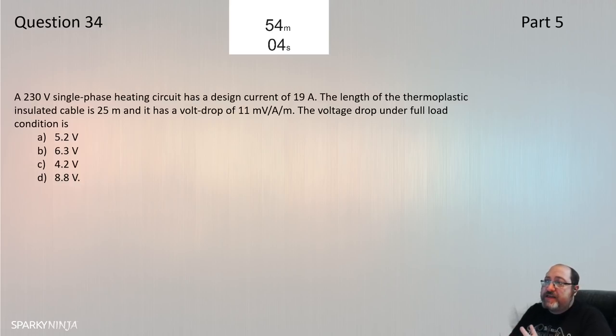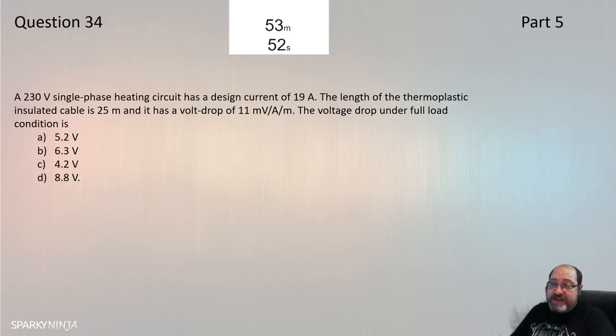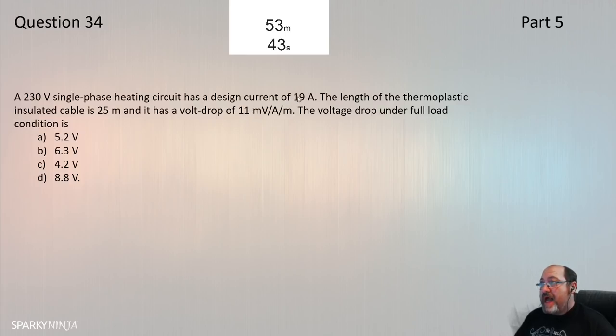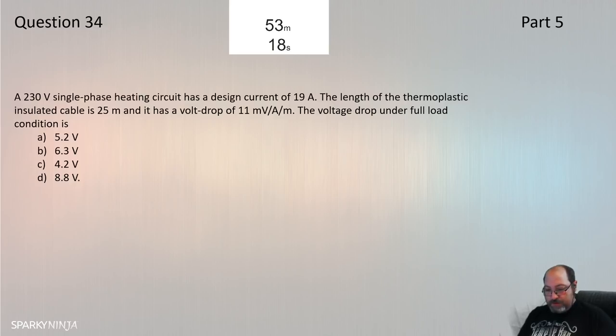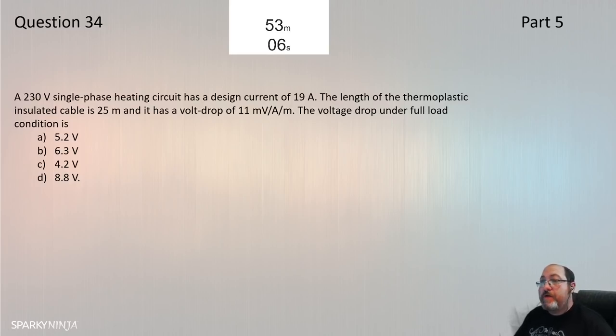Question 34: A 230V single phase heating circuit has a design current of 19A. The cable length is 25m and has a volt drop of 11 mV/A/m. The voltage drop under full load is: 11 × 19 × 25 = 5225 mV ÷ 1000 = 5.225V, approximately 5.2V. Question 34 is A.